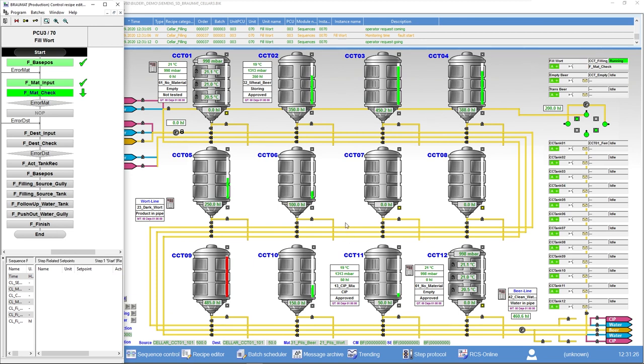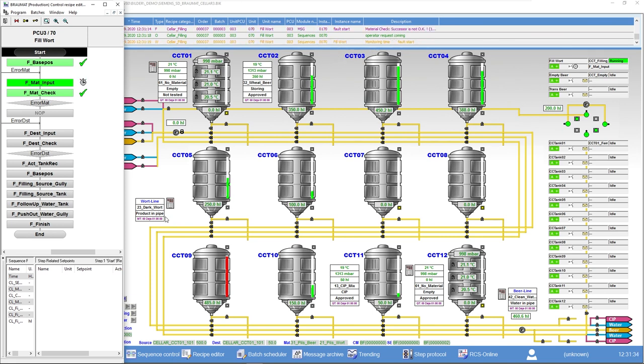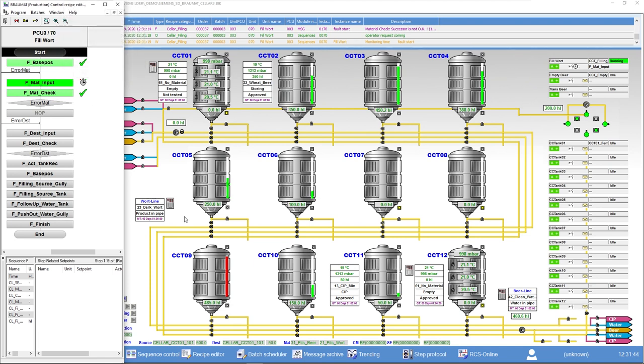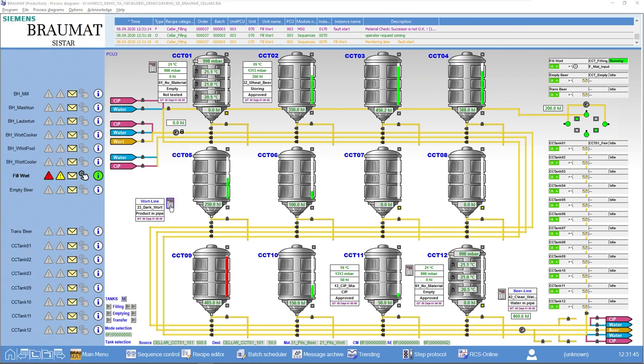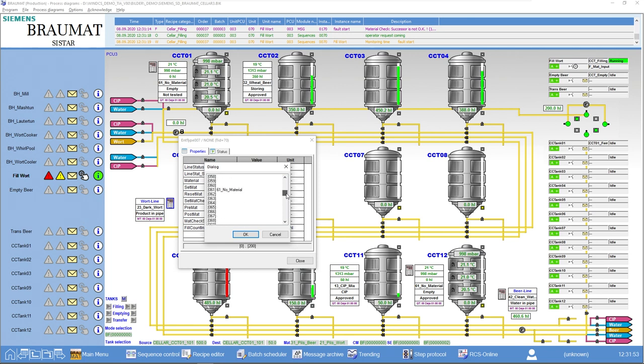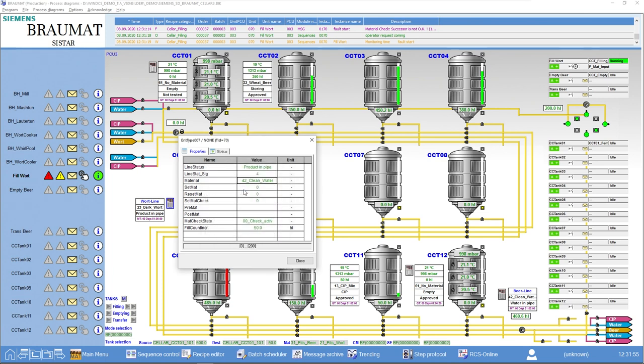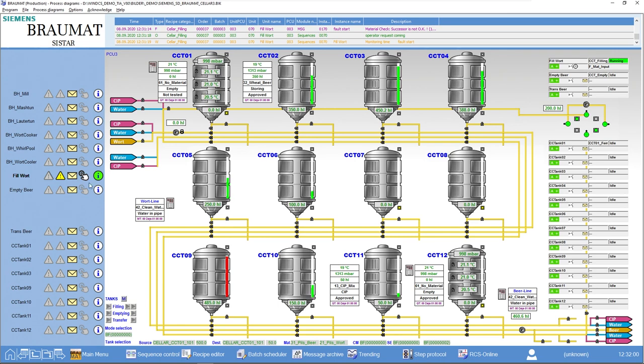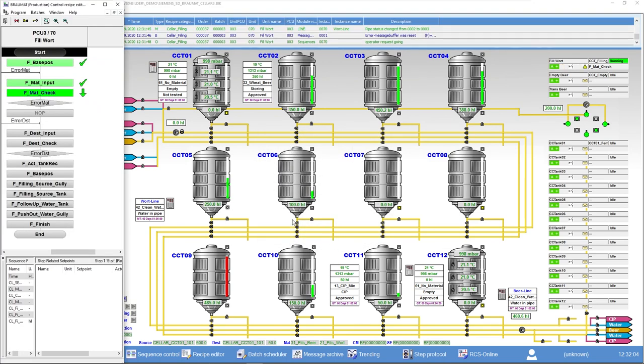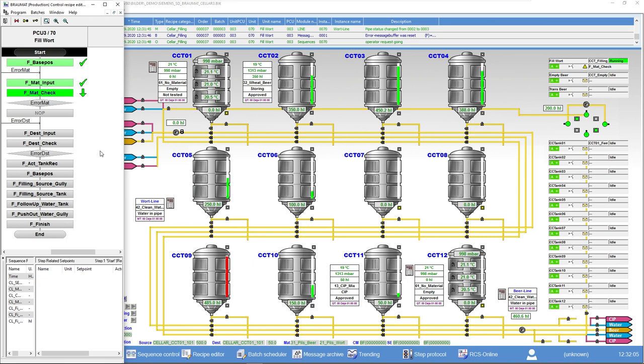It activates the subsystem accordingly and we are now requested via operator request to reconfirm that the Pilsner wort material is the one we want. A material check is carried out which duly fails because I have a material rule violation. Now it either wants a different, new material to be transferred or I do it differently. I correct my mistake and tell it that yes, of course, this pipeline has been cleaned. I acknowledge the error, re-execute the operator request and now we see that the material check works.